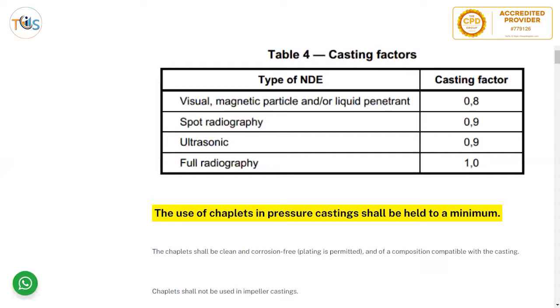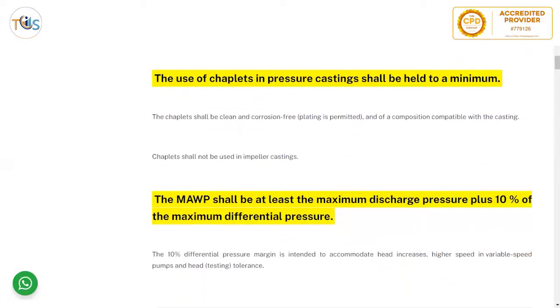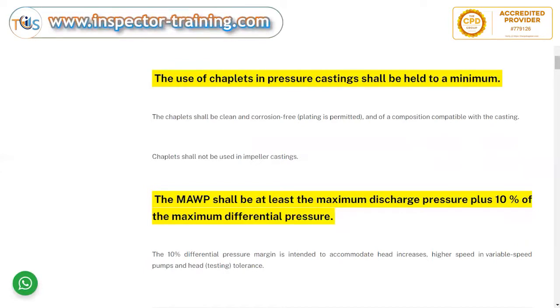You can also decrease design thickness based on pressure using the casting factor. The use of chaplets in pressure castings shall be held to a minimum. Chaplets are used to keep the mold in place and melt during pouring, but if a chaplet doesn't fully melt it can cause casting defects such as laminations and porosity. Chaplets shall be clean and corrosion-free; plating is permitted if composition is compatible with the casting. Chaplets shall not be used in impeller castings because impellers are rotating and it is too risky.